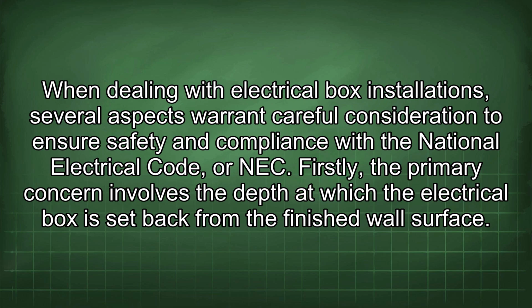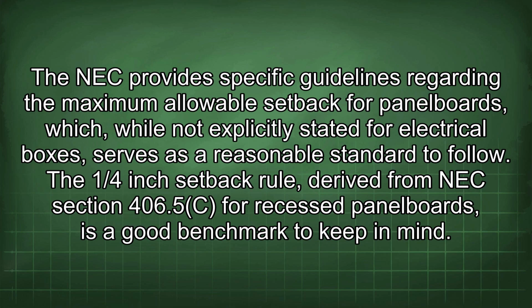When dealing with electrical box installations, several aspects warrant careful consideration to ensure safety and compliance with the National Electrical Code, or NEC. Firstly, the primary concern involves the depth at which the electrical box is set back from the finished wall surface. The NEC provides specific guidelines regarding the maximum allowable setback for panel boards, which, while not explicitly stated for electrical boxes, serves as a reasonable standard to follow. The 1/4 inch setback rule, derived from NEC section 406.5c for recessed panel boards, is a good benchmark to keep in mind.